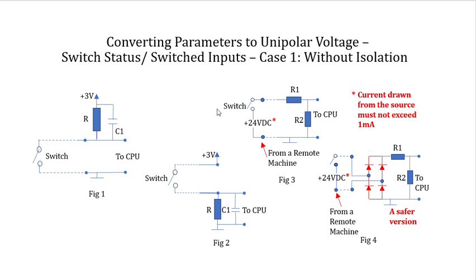Now there is another way in which switches are connected - we call it switched inputs. The input is 24 volts and it is switched. So if this switch is closed, then 24 volts will get applied like this. There's a potential divider, R1, R2, so it will be attenuated to a safe value.